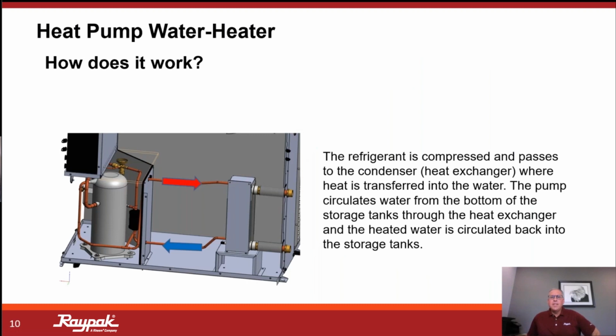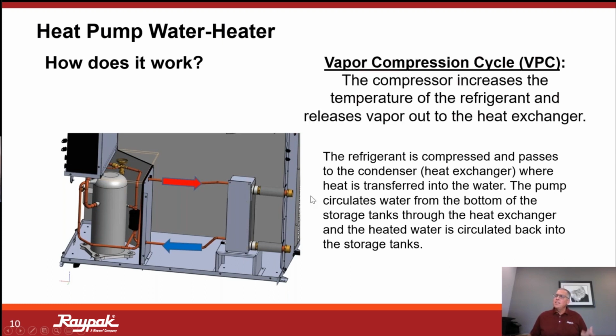And sometimes the heat pump technology might seem a bit intimidating, but the beauty of this system and its design is that the refrigerant side is all self-contained. An installing contractor is not going to need to interact with the refrigerant. It is a self-contained closed circuit where the compressor is going to take that vapor compression cycle, extract that heat, and send it into one side of a brazed plate exchanger. On the other side of that brazed plate exchanger, we're going to be pumping our fluid in, counterflowing, extracting the heat, and then sending it out to storage. So that vapor compression cycle is not something you need to be concerned about.